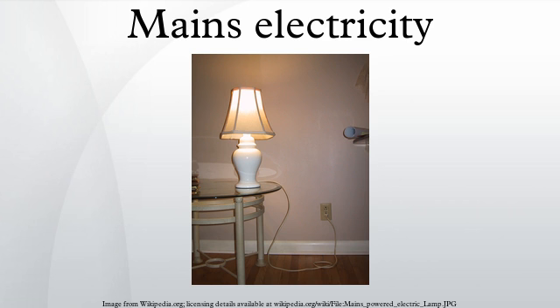Voltage regulation: to maintain the voltage at the customer's service within the acceptable range, electrical distribution utilities use regulating equipment at electrical substations or along the distribution line. At a substation, the step-down transformer will have an automatic on-load tap changer, allowing the ratio between transmission voltage and distribution voltage to be adjusted in steps. For long rural distribution circuits, automatic voltage regulators may be mounted on poles of the distribution line. These are auto-transformers, again with on-load tap changers, to adjust the ratio depending on the observed voltage changes. At each customer's service, the step-down transformer has up to 5 taps to allow some range of adjustment, usually plus or minus 5% of the nominal voltage. Since these taps are not automatically controlled, they are used only to adjust the long-term average voltage at the service and not to regulate the voltage seen by the utility customer.